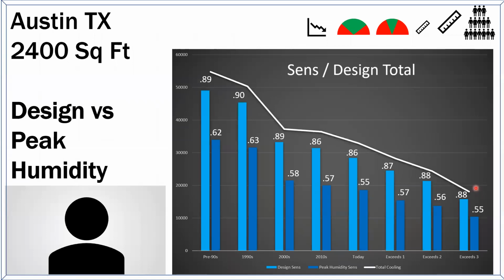The box on the wall, that's a thermostat. And the thing that tells the air conditioner to run senses temperature, that's what it does. So really, it doesn't actually matter what the latent load is. When you want to look at run times, it's what the sensible load is that matters. And so my design sensible load on my design day compared to the total load on a hot day was 90%. We've established that.